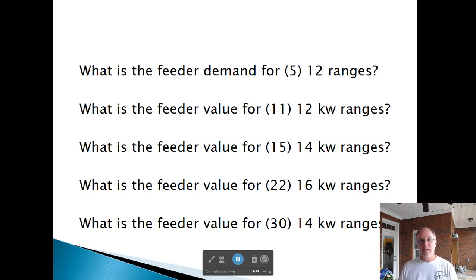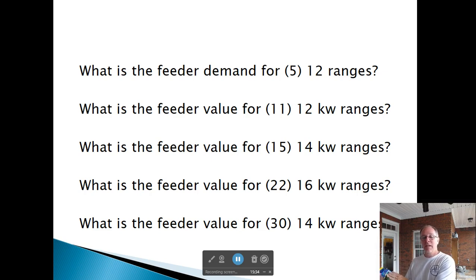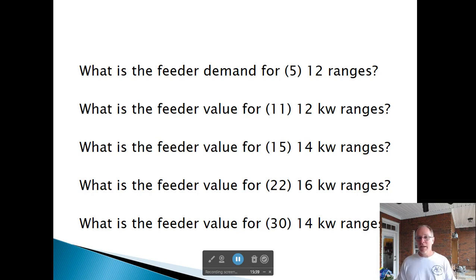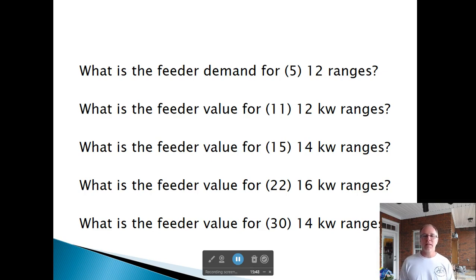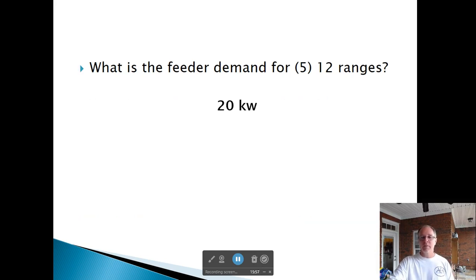If it's 13, 14, or 15 kW, you still add the over-12 multiplier after getting your Column C answer. But you don't have to turn to the table anymore. If a question asks for the feeder demand of five 12 kW ranges, the answer is 20 kW — boom, done. That's the little secret; it works every time for Column C questions.